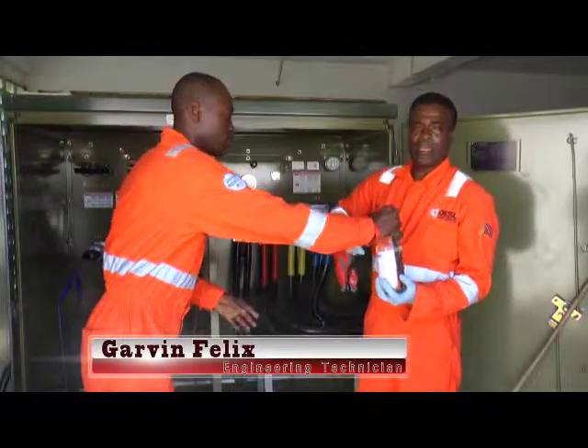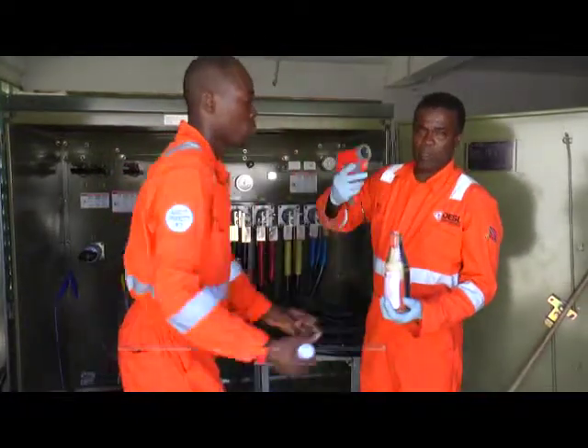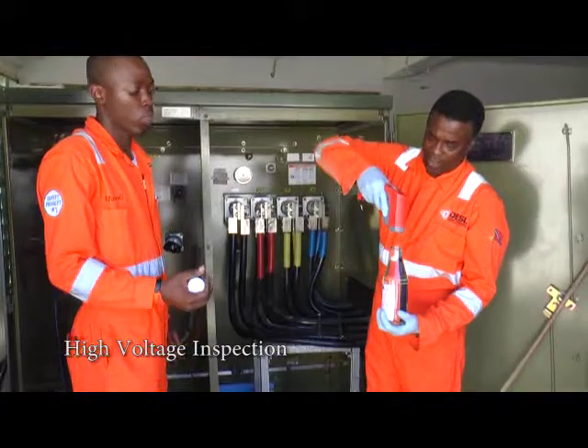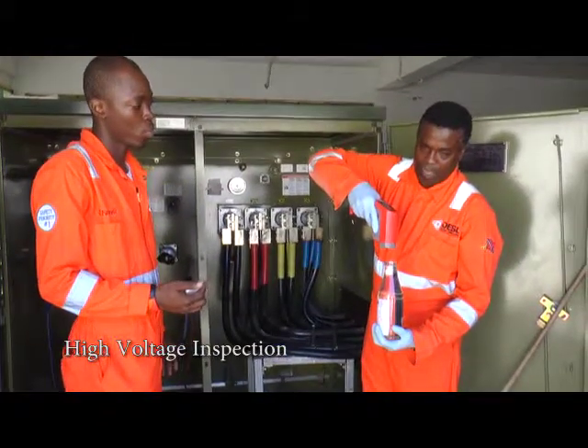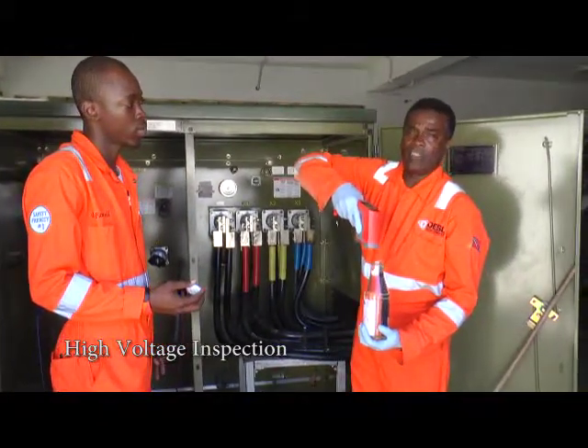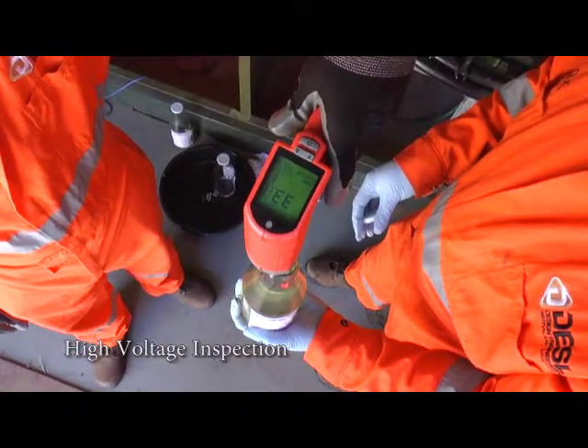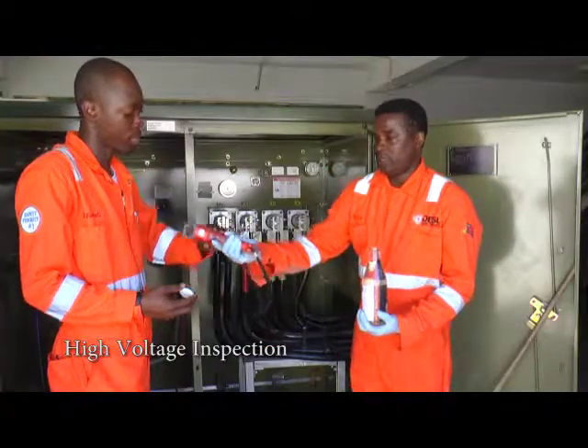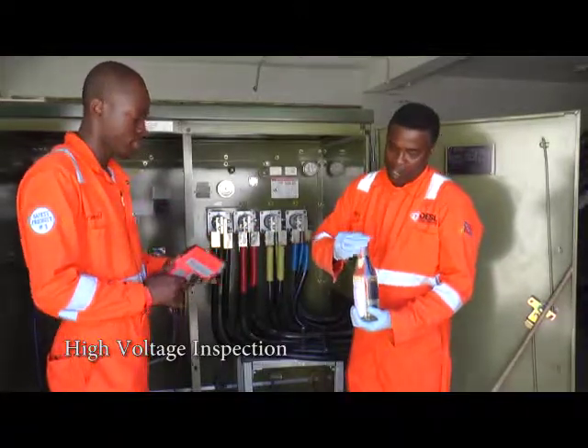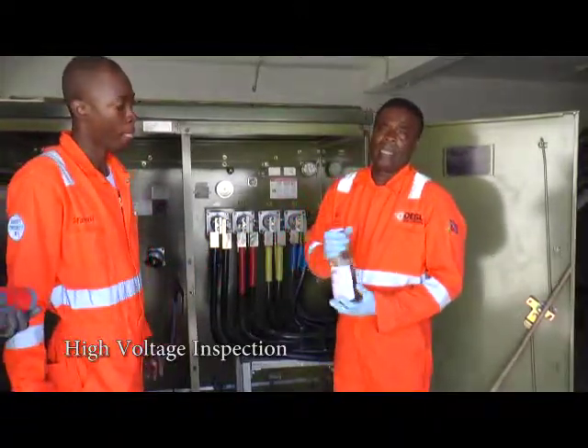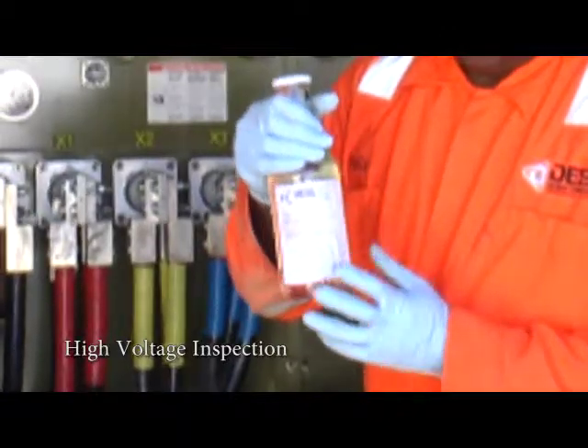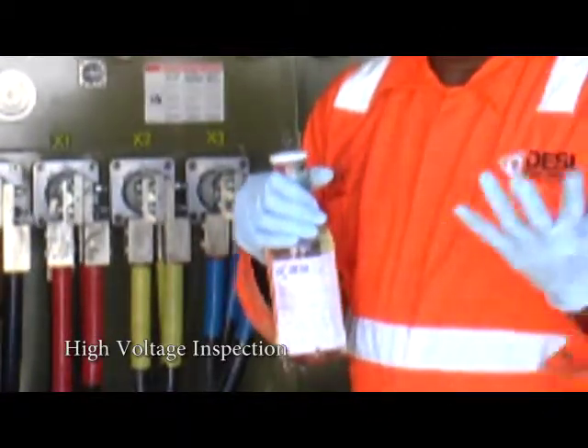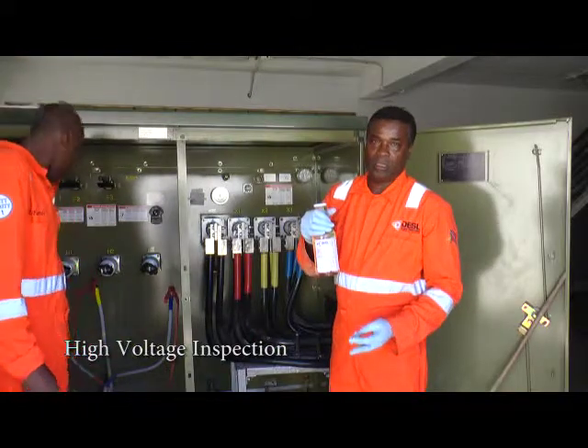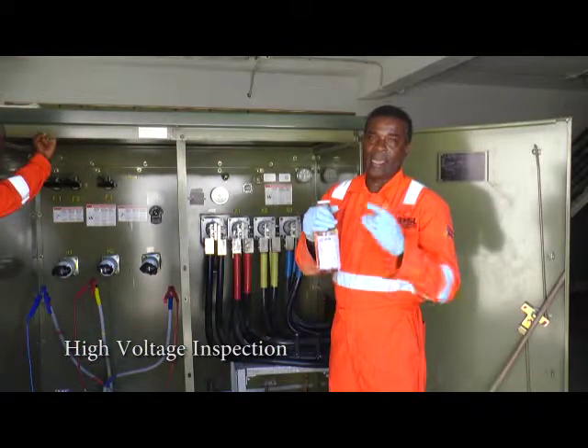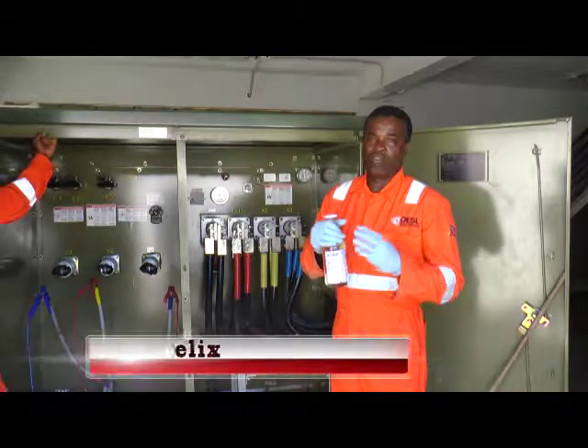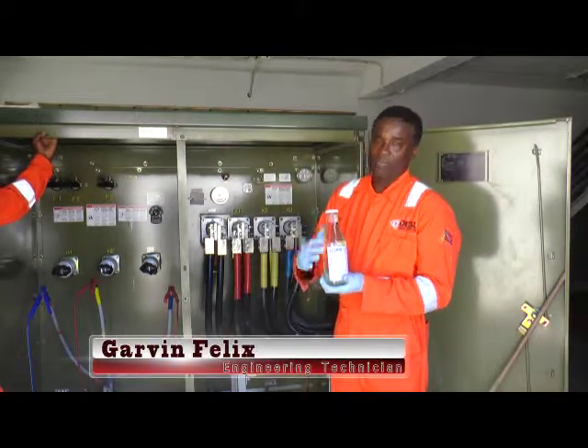After we take the oil sample, we take a temperature because we want the temperature of the oil, so that we can make a calculation of the age of the transformer, the life of the transformer. So we take this temperature. The oil goes to the lab. What we look for in the lab is dielectric strength, moisture content, and acidity. Those are the three main tests we look for in the oil.